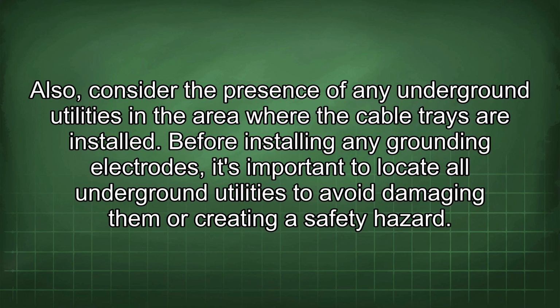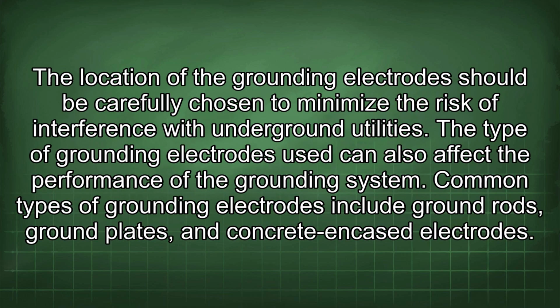Also, consider the presence of any underground utilities in the area where the cable trays are installed. Before installing any grounding electrodes, it's important to locate all underground utilities to avoid damaging them or creating a safety hazard. The location of the grounding electrode should be carefully chosen to minimize the risk of interference with underground utilities.